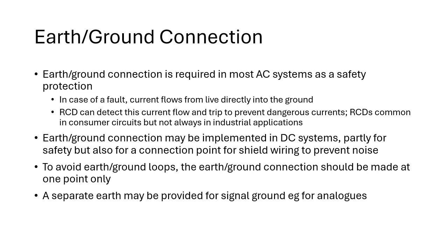Now, sometimes the downside of having everything wired to that single star is that because there's lots of current going through it, hopefully not too much because that would indicate faults elsewhere, there might be enough current going through it that there's actually noise on the earth signal itself. So what you might also find is you might have an earth or ground connection for safety, and then you'll wire a separate earth or ground to that via a single cable, and then have a separate bus bar or a separate earth connection. And what that does is it isolates the safety earth from the signal ground, and that protects you against some noise going back into circuits. So again, very important for analog circuits, particularly if you're concerned about accuracy of the signal, but also very important for safety as well. So make sure you've got a good earth ground connection, and there are various constraints about how that should work, and I think I've got a slide on that coming up.